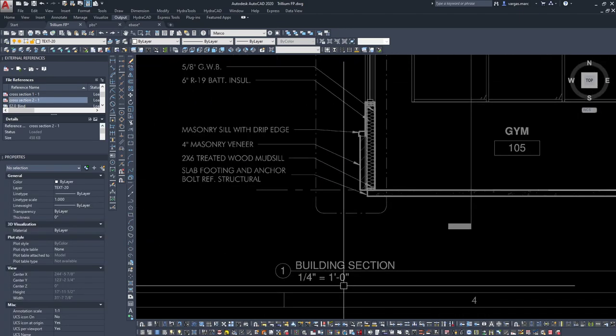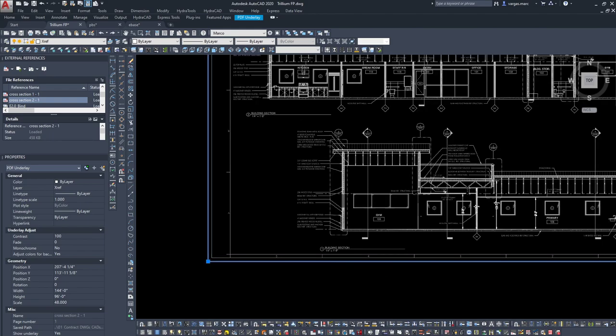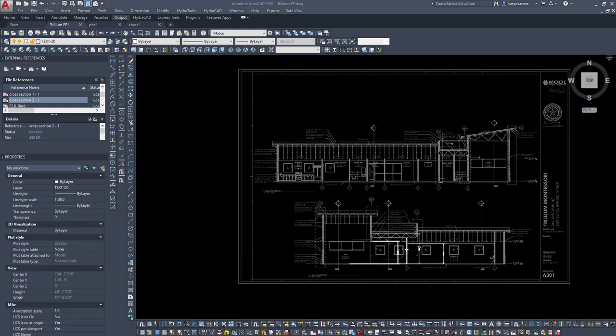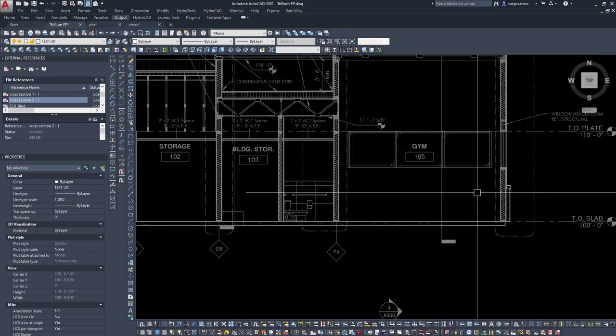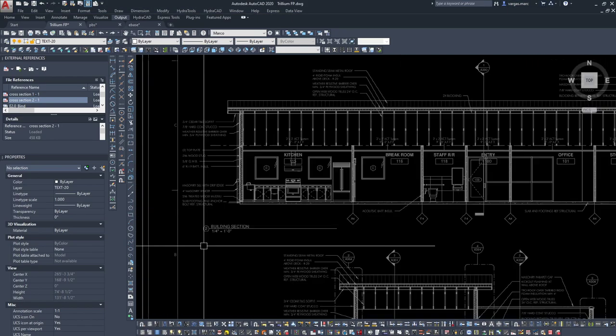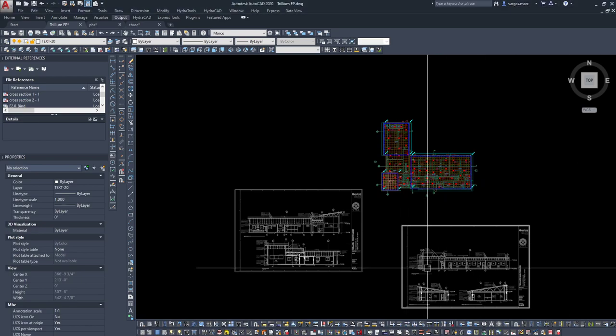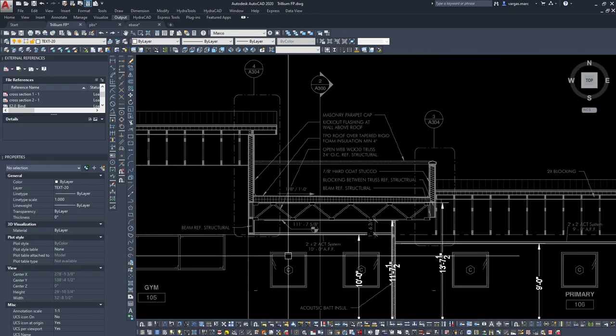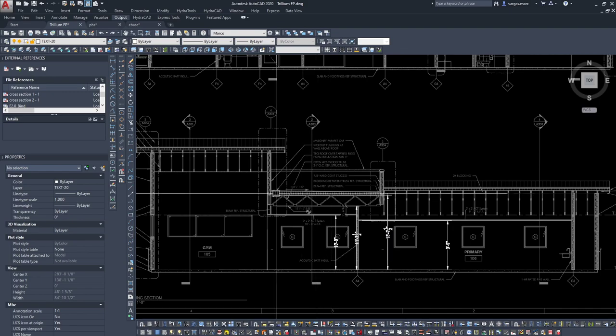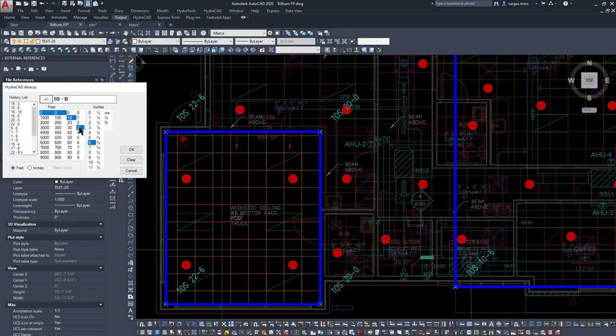When a drawing is in quarter-inch scale and you import the PDF, if you import it at a scale of 48, it'll import at the proper scale if the PDF was created directly from CAD. For an eighth-inch scale drawing, import at 96. I used to waste a lot of time figuring this out — one day it clicked and worked. So it looks like we have 13 feet 7 and a half to the top of structure in this flat area.